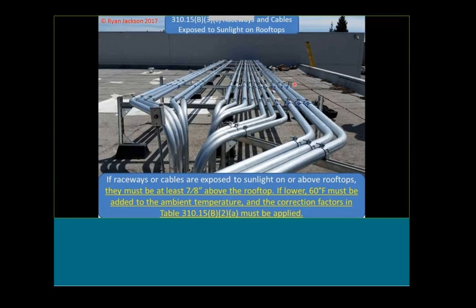If I walk up to the roof here and put my hand on this conduit, it's certainly going to be a lot hotter up there than it was down on the ground. So it stands to reason that the wire inside that raceway is also going to be hotter if it's on the roof than on the ground. That's what, I hate to use the word common sense, but that's what common sense would tell us. What we found out is common sense wasn't completely accurate. We've done a lot of research, and surprisingly, this just isn't the issue we thought it was.